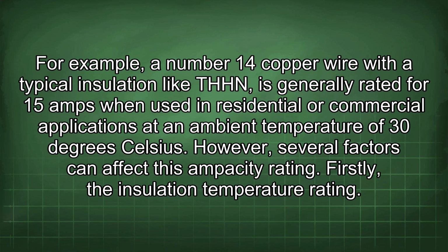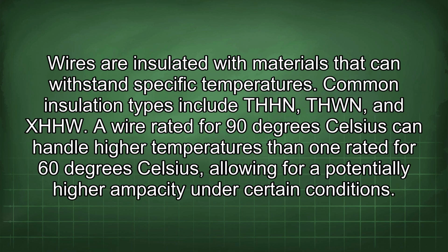For example, a number 14 copper wire with a typical insulation like THHN is generally rated for 15 amps when used in residential or commercial applications at an ambient temperature of 30 degrees Celsius. However, several factors can affect this ampacity rating. Firstly, the insulation temperature rating. Wires are insulated with materials that can withstand specific temperatures. Common insulation types include THHN, THWN, and XHHW.